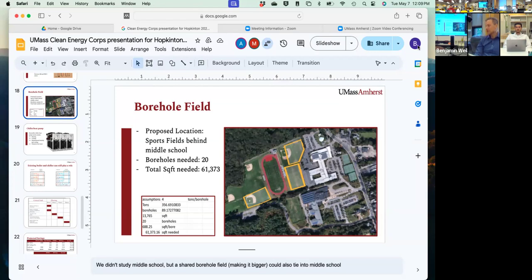And the nice thing about linking it all through the high school and then sending heated and chilled water directly to the middle school, without giving the middle school its own physical plant or its own chiller, is keeping it all under one set of controls, right? You just have pumps sending water over to here. You therefore get to rearrange the mechanical rooms. You have one manifold instead of two manifolds. So there are some efficiencies by essentially setting up a district system that feeds over here.